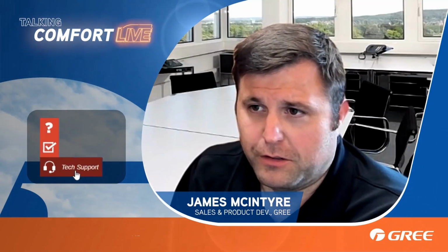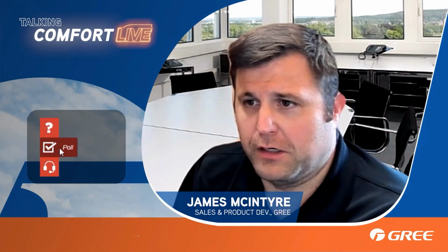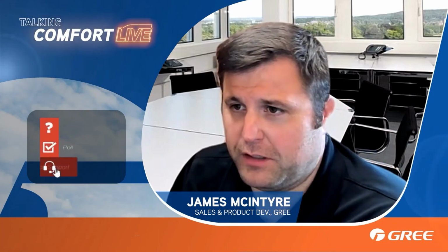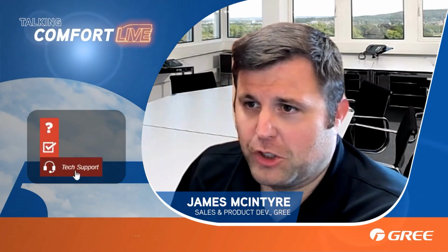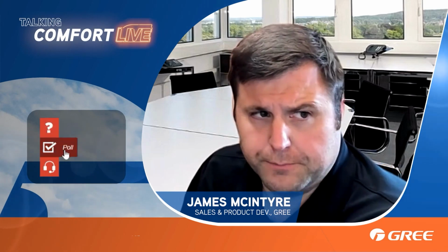And a good chunk of our equipment, I mean, all of them, are electronically limited. So in the case of at least a couple of models, the maximum amount of amp draw that it could theoretically produce is going to be about 19 amps before it would shut down on the error code, for example. So I believe that's something I would keep in mind if I was trying to size a generator for a system like that.